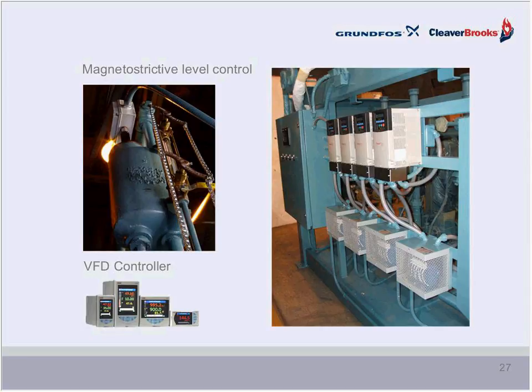I also wanted to mention that this technology can be applied to variable speed feed pumps and modulating feed water valves too. In this case, we need to install a pressure transducer between the discharge side of the pump and the feed valve. And as the feed valve modulates from open to closed position, the signal from the transducer varies and is sent to the VFD controller, increasing or decreasing the motor's speed.